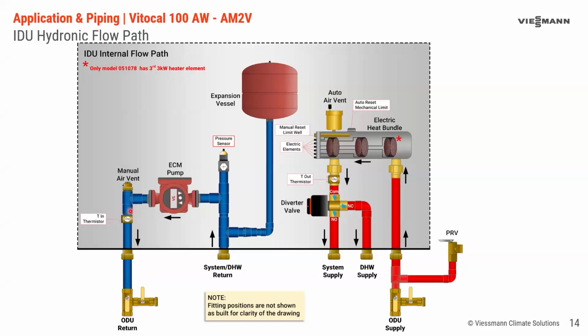So just a quick run through of the things that are happening. What we're going to talk about today is the connections between indoor and outdoor unit. And you can see that the indoor and outdoor unit are connected here through these two pipes here. And then once it's inside, the indoor unit is responsible for adding the electric heat when it's necessary and sending it to DHW or to the buffer tank, and then everything comes back to here.